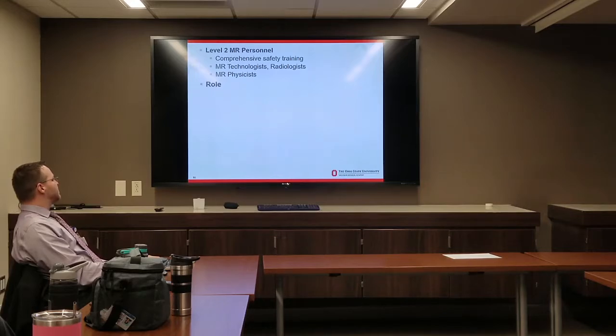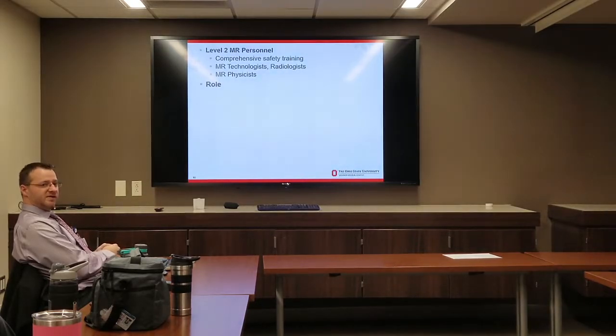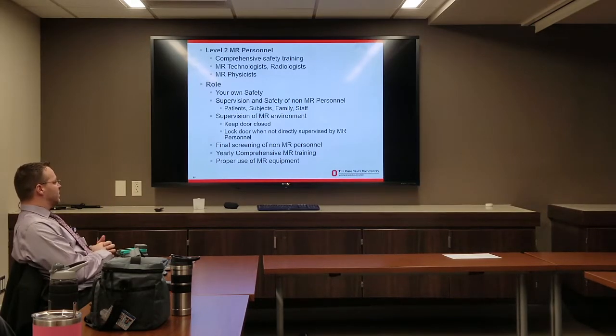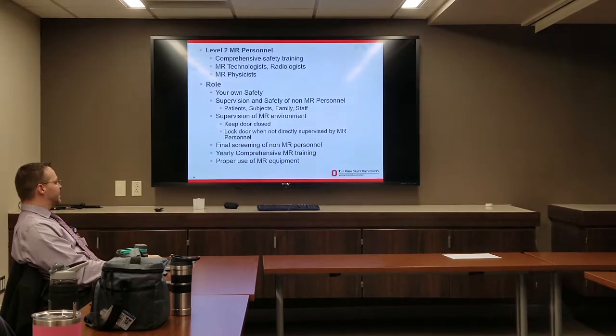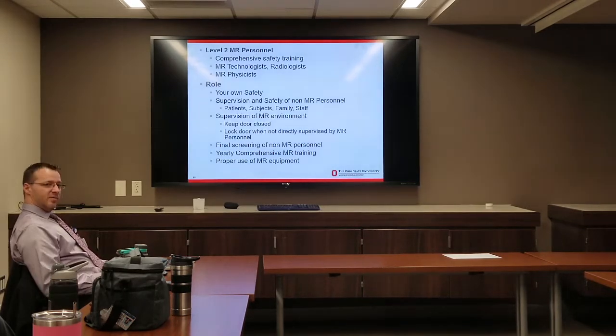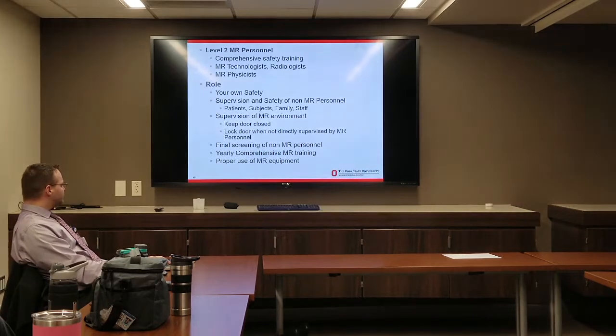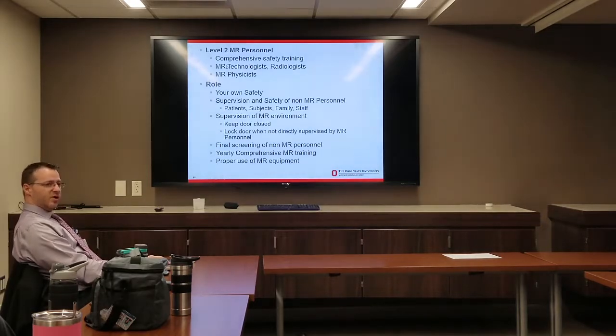Level 2 personnel receive comprehensive safety training — this includes technologists, radiologists, and MR physicists. Their role is their own safety and supervision of the magnetic environment and everyone in it, including patients, subjects, family, and staff. They keep the door closed, monitor the area, and are responsible for the final screening of MR patients — they should be the last person to check the screening forms before the patient enters the room. They must have yearly comprehensive MR training and be trained in proper use of MR equipment.